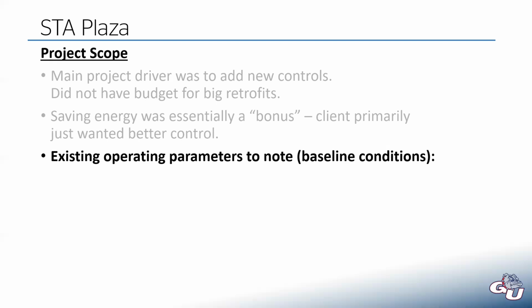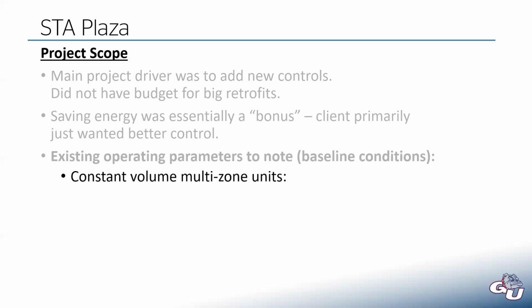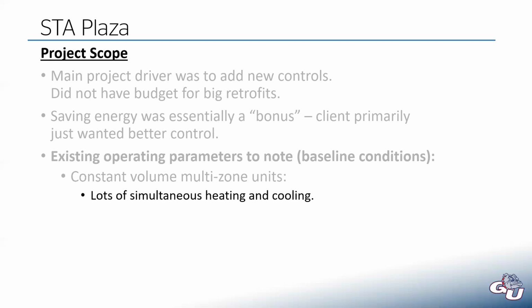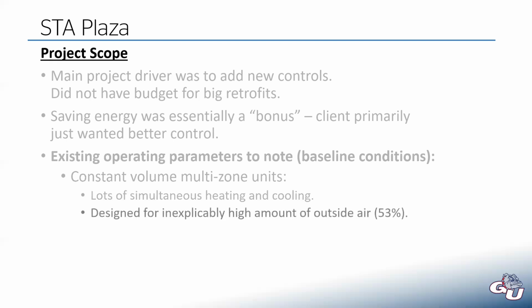So some of the existing operating parameters. So this is how it was when we found the building. These are the baseline conditions. I mentioned they have constant volume multi-zone units. And if you recall, constant volume multi-zone units always have lots of simultaneous heating and cooling. Because they're blending the hot and the cold air all the time, you're just constantly having those two systems fight each other. The other thing we discovered, for some reason, these multi-zone units were designed for an extremely high amount of outside air, about 53% of their total supply air.